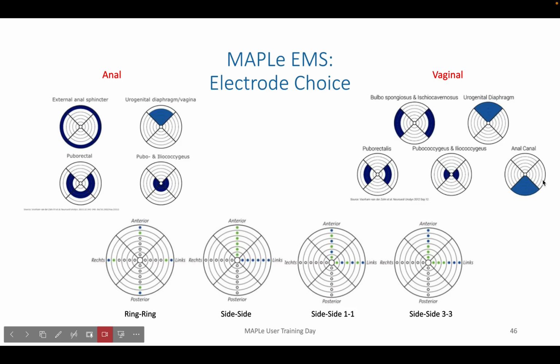With your electrical stimulation, you can have different electrodes activated to target different areas within the pelvic floor. So you have a ring-to-ring option. So here in the bottom left picture, you can see blue and green for rings 5 and 6. So here, for instance, if you're treating the external anal sphincter, you can treat by ring to ring with rectal insertion of the probe, and you are activating the external sphincter by switching on only electrodes 5 and 6.